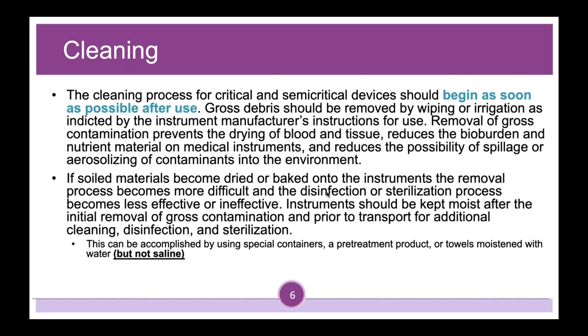I cannot emphasize the importance of cleaning. The cleaning process for critical and semi-critical devices should begin as soon as possible after use. What does that mean? That means that we should not have equipment, devices, instruments, whatever term you want to use, sitting and just waiting to be reprocessed.